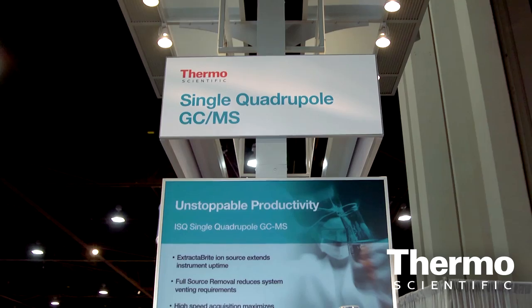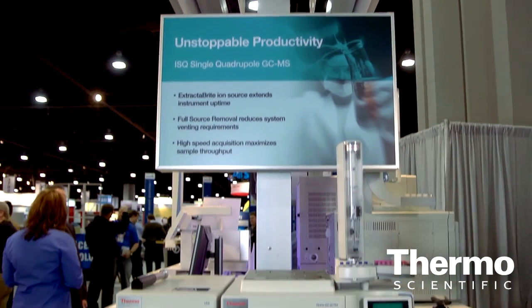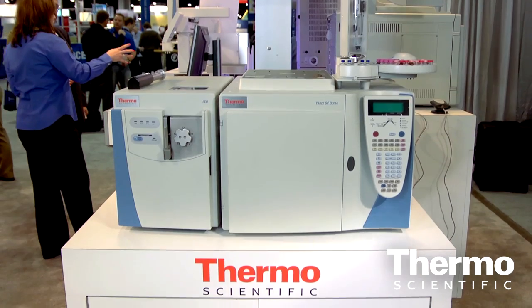That's our main contribution here at PITCON in the mass spectrometry area. When we move to chromatography, we have a new GCMS system. It has uptime of basically 100%. You can automatically pull out the entire source and put in a new source without breaking vacuum or killing the system, which is very important for high throughput labs.